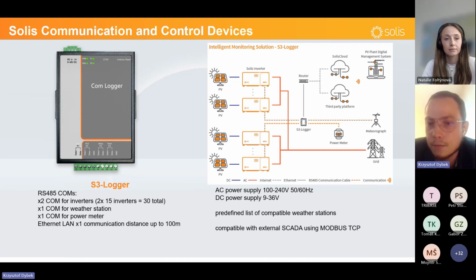One thing needs to be mentioned, this S3 logger is still under development, and for example, EPM function still doesn't work properly. So if you need limiting power of the plant right now, it's better to go with EPM device. So after we upgrade this software, everything will be fine. But right now, I do not recommend to use it if you want to have zero export limitation on site.